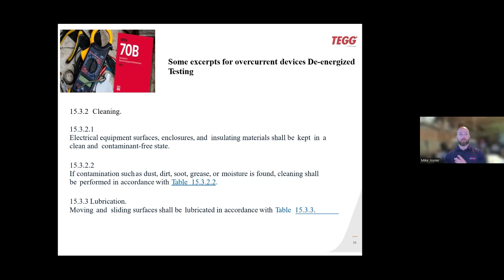It's just so we go inside there and make sure that everything is clean, working properly, closing up any holes or any potential entry points they might have in there, and then relubricating things. Because if there was any kind of fault downstream, and God forbid these breakers aren't opening, which they should, or tripping the way they should, because it's not properly exercised or greased, that can seize the breaker shut and just continue this arc and arc and arc. So it is very imperative to make sure that everything is taken care of in maintenance properly.